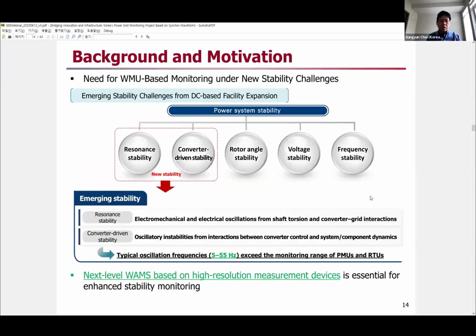The IEEE recently emphasized new stability issues, other than the historical stability issues: resonance and converter-driven stability. Resonance means some kind of interaction between converters and the grid, or converters and other devices. And converter-driven stability means oscillation induced from the converter's main control logic and weak system side interactions. In these two stability types, the generated oscillation frequency is 5 to 50 hertz or so, sometimes going up to 80s.